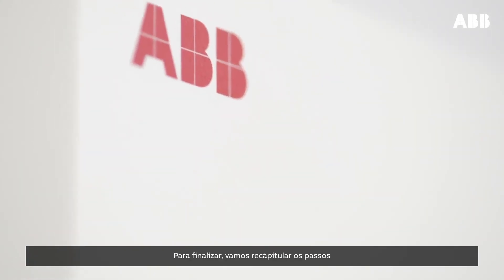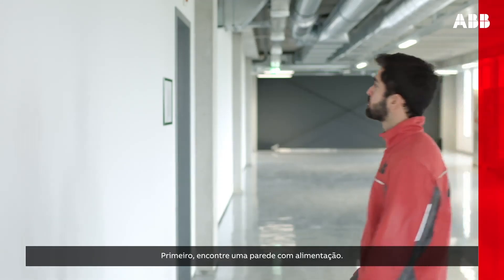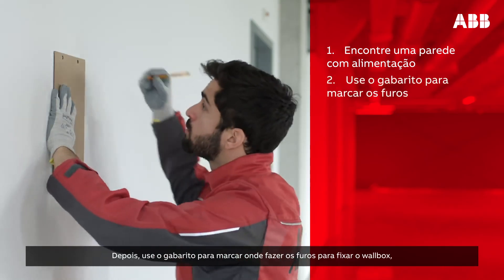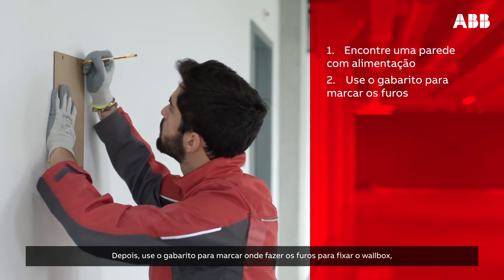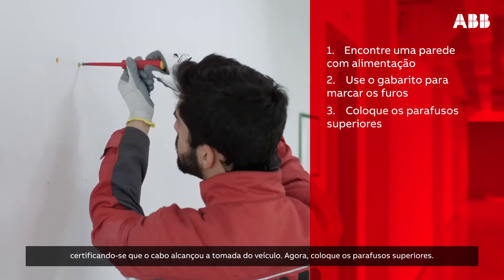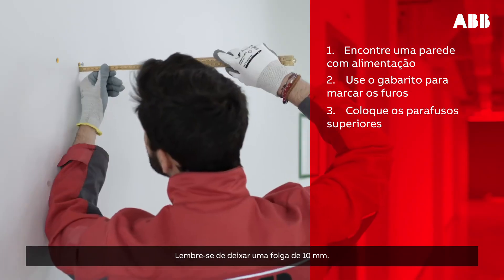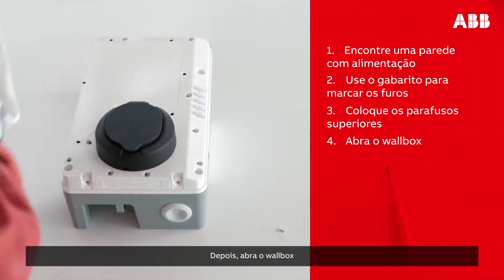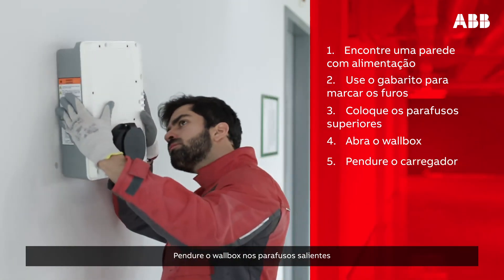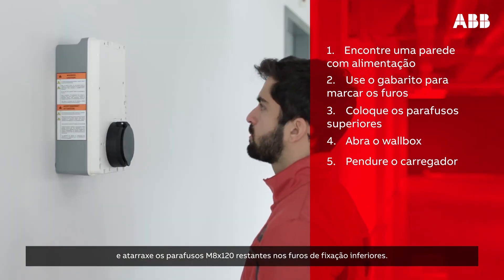Let's finish by recapping the steps involved in installing the Terra AC wall box. First, find a wall with a power supply. Next, use the template to mark where to drill the holes to mount the wall box, ensuring the cable will reach the vehicle inlet. Then, install the top screws, remembering to leave them protruding 10 mm. Next, open the wall box by removing the two screws at the bottom. Hang the wall box on the protruding screws and screw the remaining M8 by 120 screws into the bottom mounting holes.